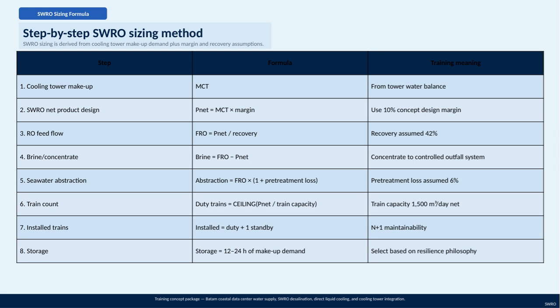Then, we determine the number of treatment trains needed by dividing the net product by the capacity of each train, which is 1,500 cubic meters per day net, and rounding up using the ceiling function. For reliability, we install one standby train in addition to the duty trains, following the N+1 maintainability principle. This ensures continuous operation, even if one train is offline for maintenance. Finally, we size the storage to cover between 12 and 24 hours of makeup demand, choosing the exact amount based on the facility's resilience philosophy to ensure continuous supply during any operational interruptions.